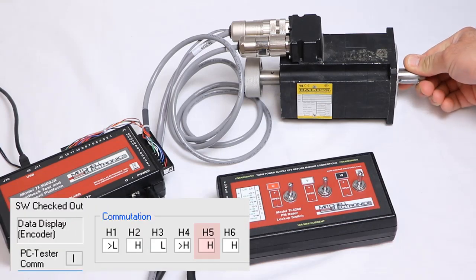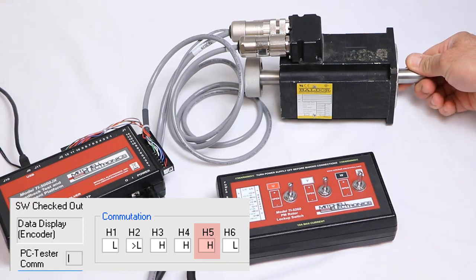If any of the signals are stuck in the high or low position while the feedback is rotated, then it could indicate a bad connection or broken feedback device.